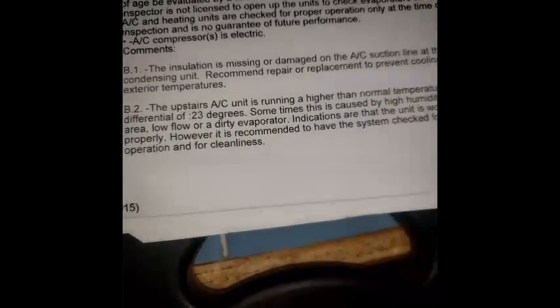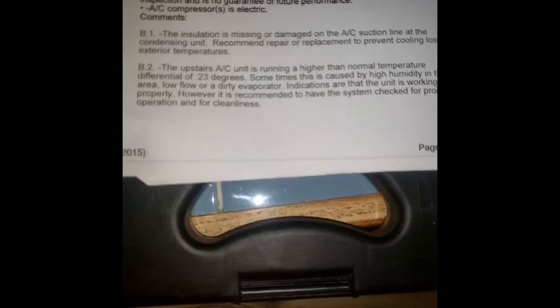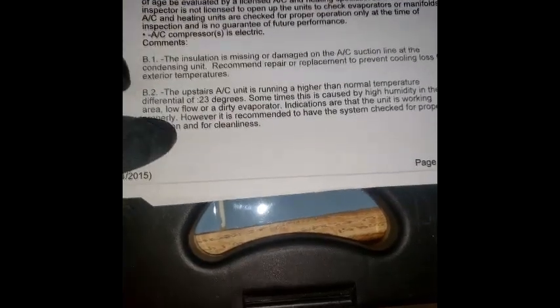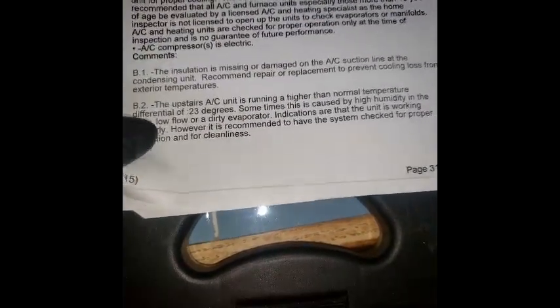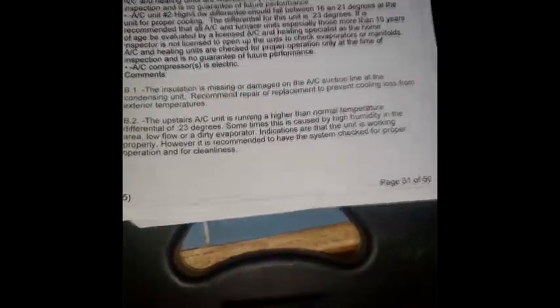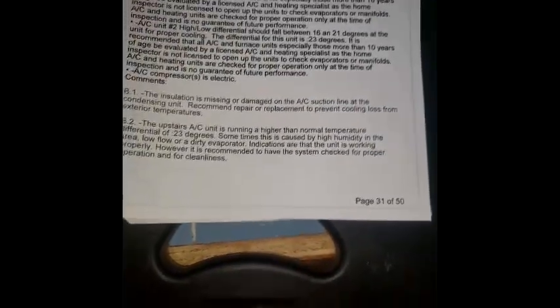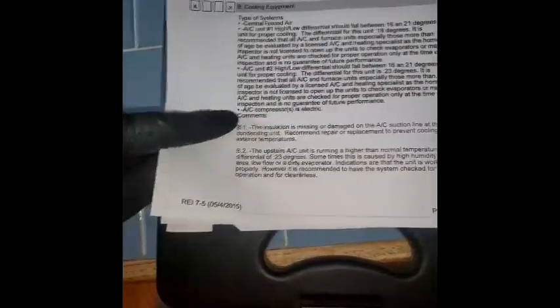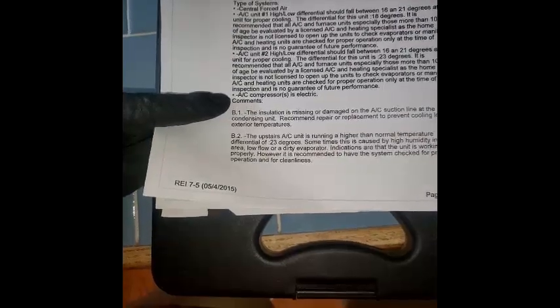We got a 23 degree differential. I'm gonna go ahead and check my pressures, I got my gauges around. I'll check the pressures while I'm here since I can't run it in AC mode. If it's low on refrigerant or something like that, I'll quote them the next time I come out.